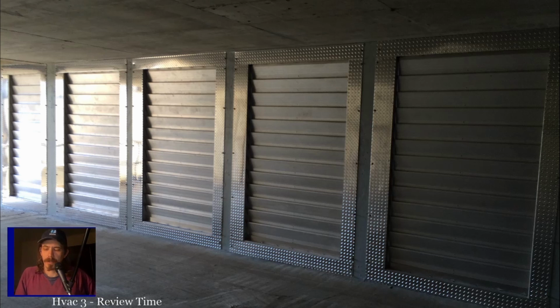But a lockout relay is a good way to make sure that if anything in that circuit fails, and if any of those switches end up tripping, then you've covered all of them. So, something you should really keep in the back of your head when you're diagnosing things, it's a really good professional way of adding a little bit extra insurance to a system relatively cheaply.